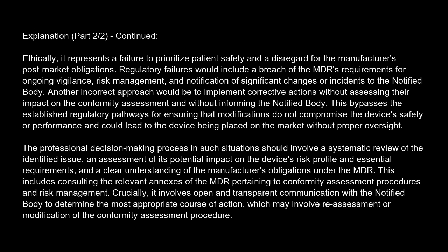Another incorrect approach would be to implement corrective actions without assessing their impact on the conformity assessment and without informing the notified body. This bypasses the established regulatory pathways for ensuring that modifications do not compromise the device's safety or performance, and could lead to the device being placed on the market without proper oversight. The professional decision-making process in such situations should involve a systematic review of the identified issue, an assessment of its potential impact on the device's risk profile and essential requirements, and a clear understanding of the manufacturer's obligations under the MDR.